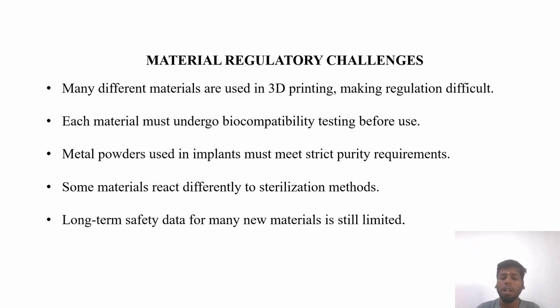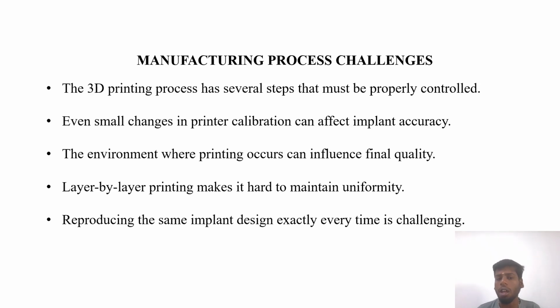Long-term safety data for many new materials is still limited. The 3D printing manufacturing process has several steps that must be properly controlled. Even small changes in the printer calibration can affect the implant accuracy. So we have to set everything in a proper way, because if a point of calibration is missed, the total implant accuracy will change, and it may cause problems. The environment we are printing in can also influence the final quality. We have to print in a safe environment that does not affect the implants while we are manufacturing.